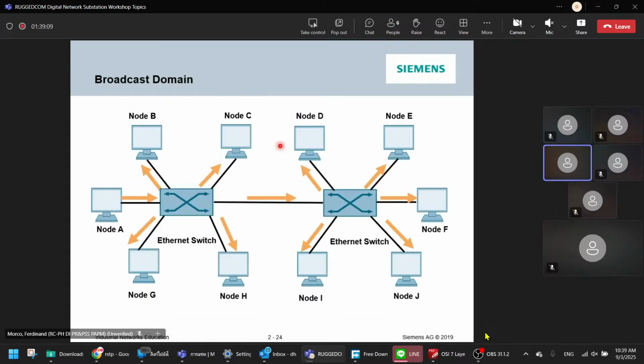Before that, I have one more question about the priority. We talked about first come, first served, right? But for 61850 GOOSE and SV we need priority. That is also in priority for GOOSE, sample values, and PTP, or Precision Time Protocol. You put VLAN tags. In VLAN tags you can provide priority. By default it's 4. If we did not use VLAN, can we set the priority? Yes, all of the ports will have a default priority set to 1. Sorry, 1 or 0.